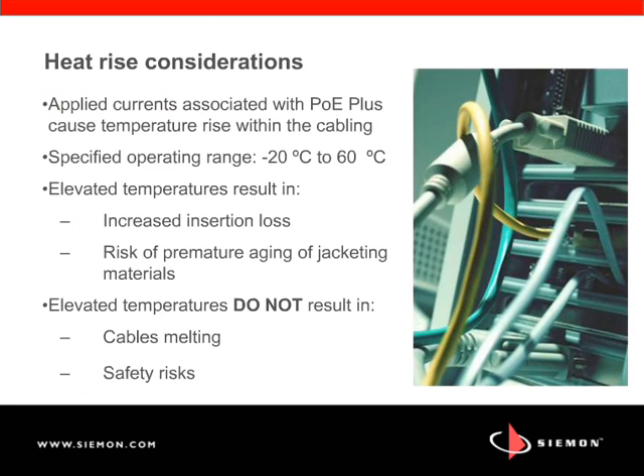We talked about arcing conditions. When I specify the requirements for the PSE output power and the power received by the power device, as I mentioned, there's a difference. There are some losses in there. Those losses occur as a result of impedance within the cable, and those losses create an artifact, which is increased temperature rise within the cable bundle. So this has implications for the operating range of structured cabling, which is specified to operate up to 60 degrees C. We don't want excessive temperature rise in the bundle that exceeds that 60 degree C operating environment, so that's something we need to talk about.